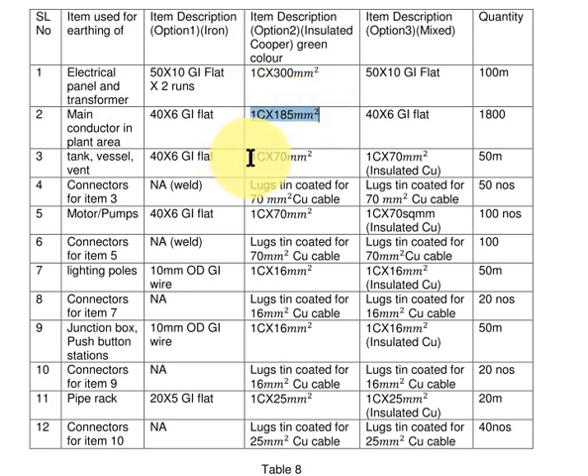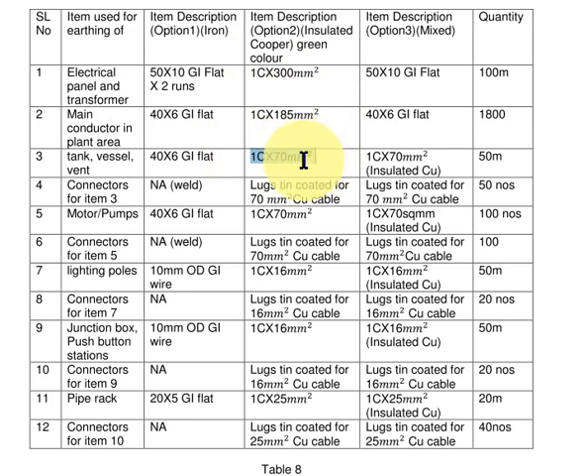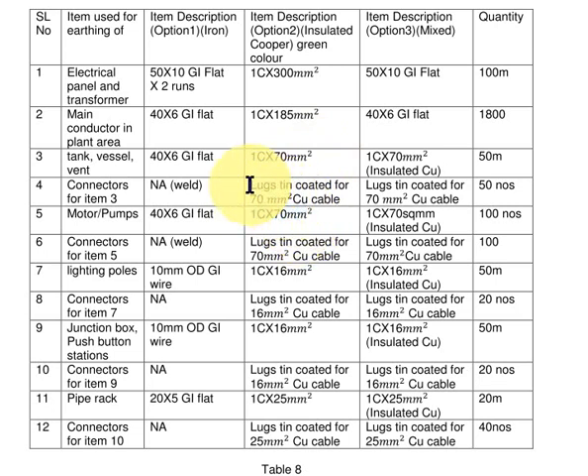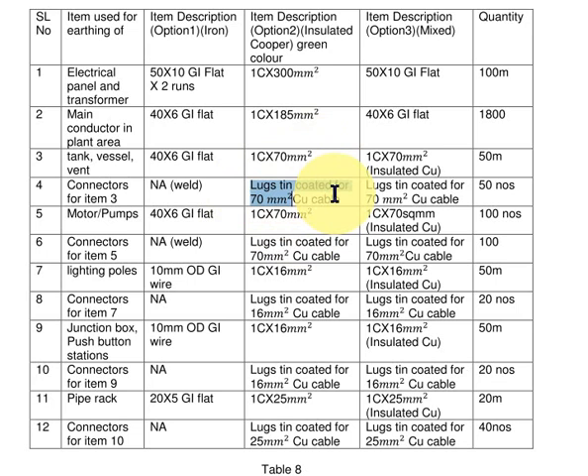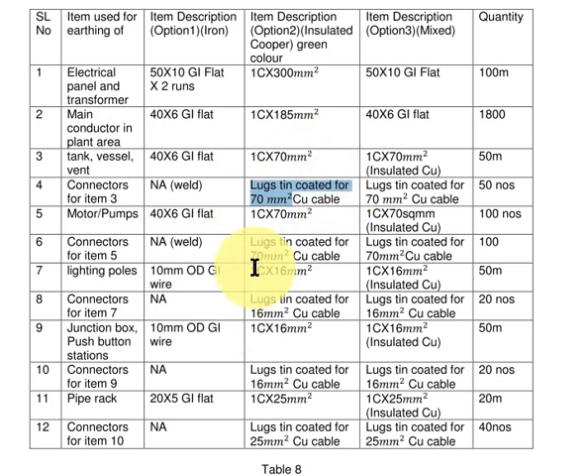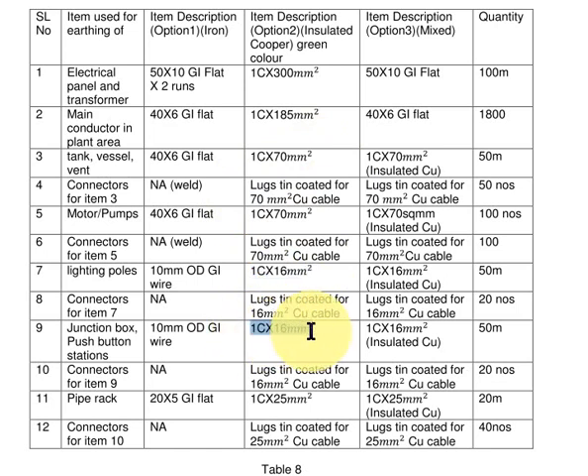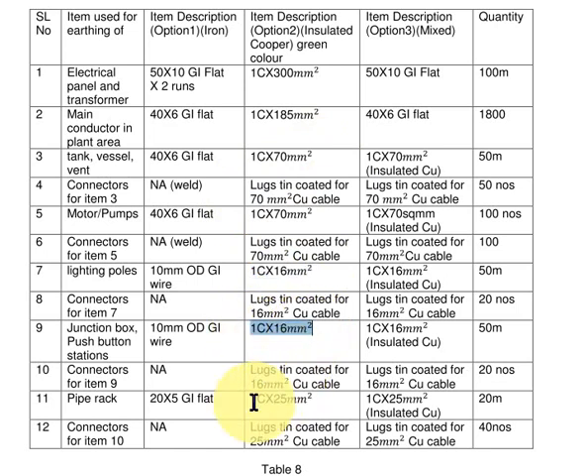For tanks, vessels, and vents, single core 70 mm² copper was used. For motor and pump, single core 70 mm² copper. For connecting, we use lugs tin coated. For lighting pole, single core 16 mm² cable was used. For JB also, single core 16 mm² cable was used.